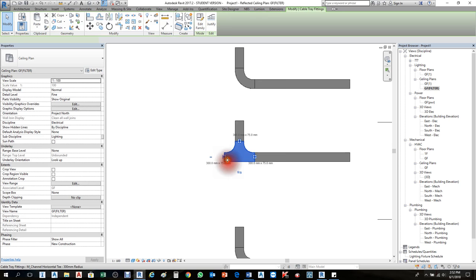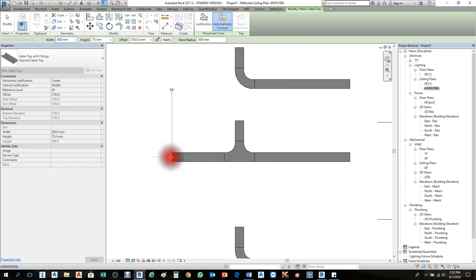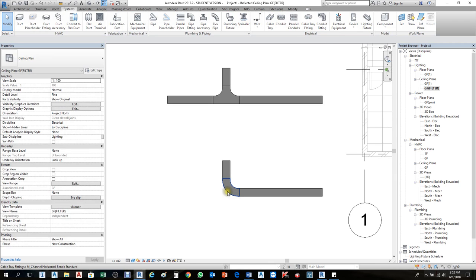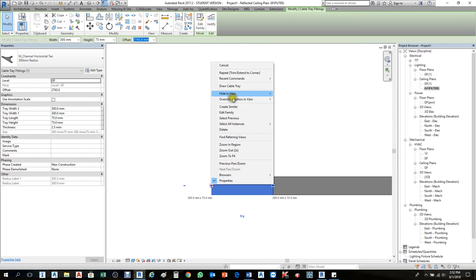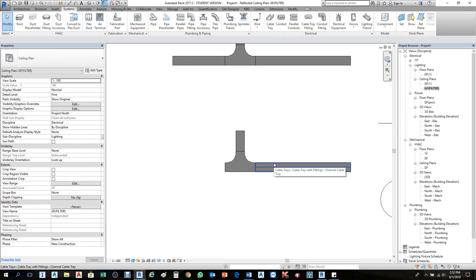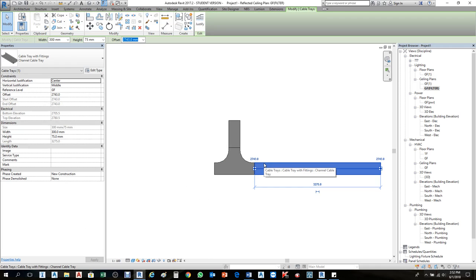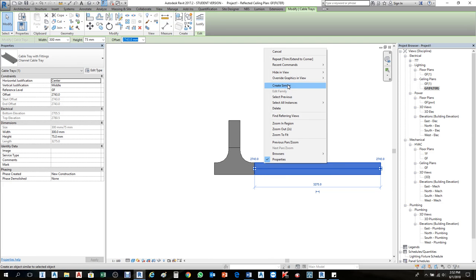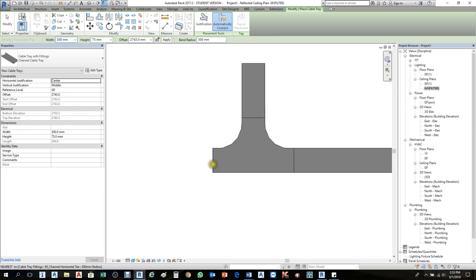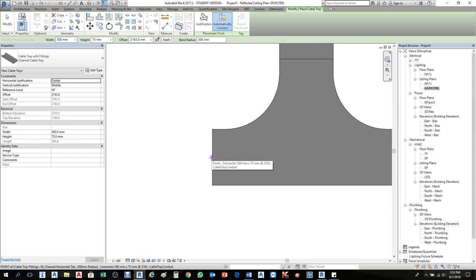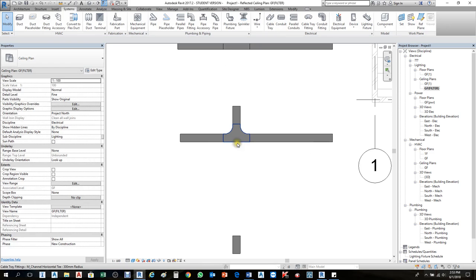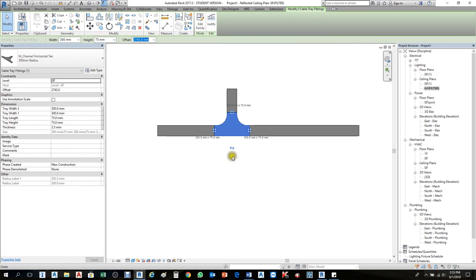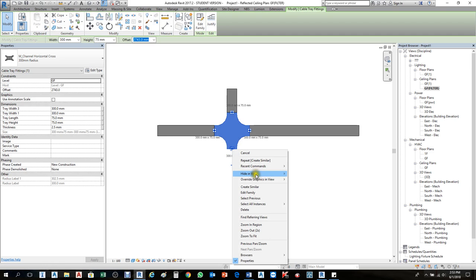After trimming, if you click on a fitting you'll see two plus symbols — click a plus symbol to continue drawing another cable tray from that fitting. For additional connections, right-click on the dot to draw from there. Alternatively, click an existing cable tray, right-click, and choose Create Similar — it gives you the same size, width, height, and offset. Then snap to the center point and continue drawing.